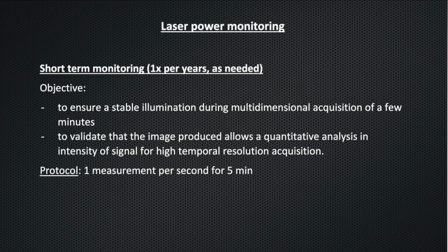The protocol of measure requires the power meter with a data logger to register the data. You need to perform one measurement per second for 5 minutes.